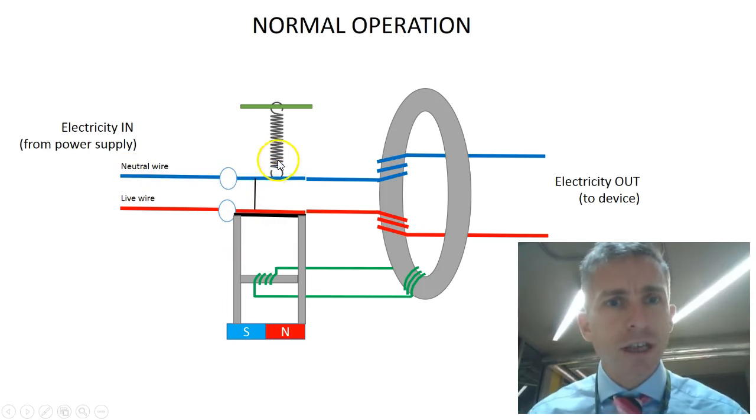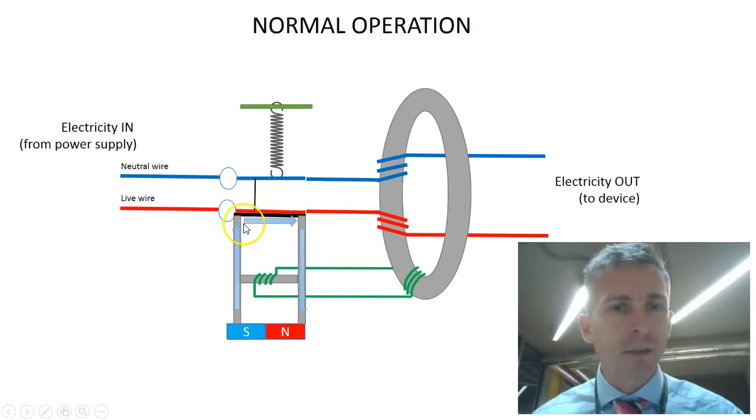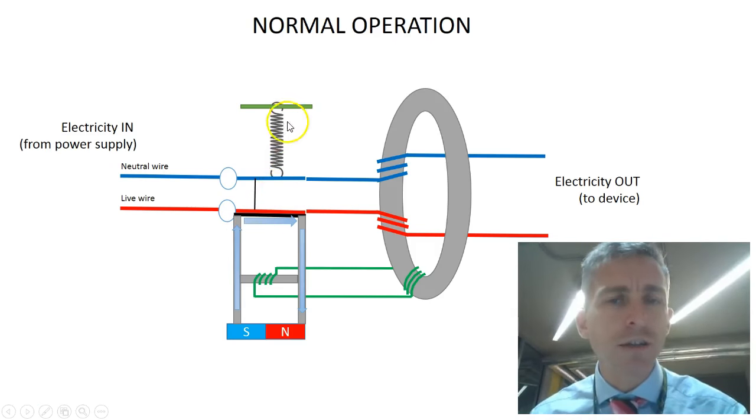Now the switch gear is held in place, or it's pulled up by this spring, but it's held in place by this magnetic arrangement here. The permanent magnet produces a magnetic field which flows through the iron part of the switch gear and back down to the north pole of the magnet. And so they are attracting the iron and it holds it down in place. It has to be a sufficient force to withstand the pulling of this spring.